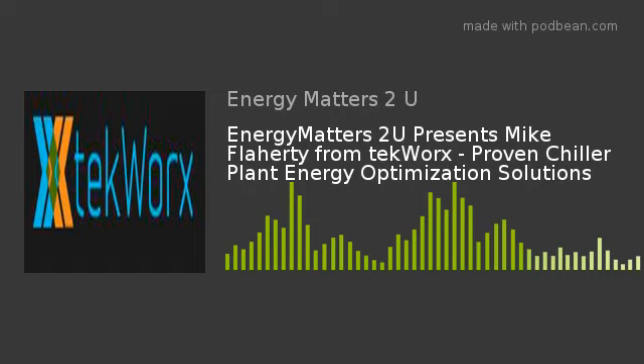A better metric, if you have the wherewithal to figure it out, is your ton-hours - roughly your average load times the number of hours you run throughout the year. If you multiply those two metrics together and get a number around 1.5 to 2 million, you can usually figure a project will work. So that's the rule of thumb we give people: about 500 tons installed capacity or greater.